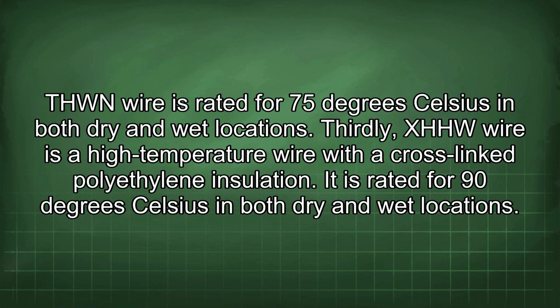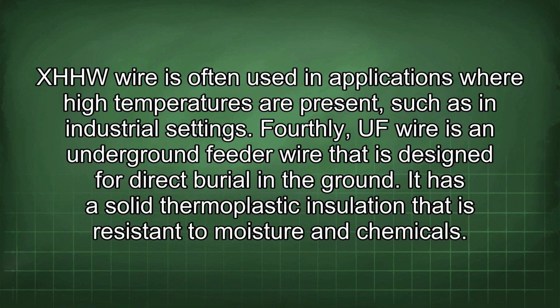Thirdly, XHHW wire is a high-temperature wire with a cross-linked polyethylene insulation. It is rated for 90 degrees Celsius in both dry and wet locations. XHHW wire is often used in applications where high temperatures are present, such as in industrial settings.